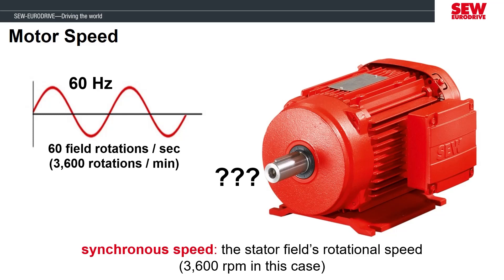If we took this same motor to Europe and connected it to the power supplies there, the motor's synchronous speed wouldn't be 3,600 RPM but would be 3,000, because they supply 50 Hertz.